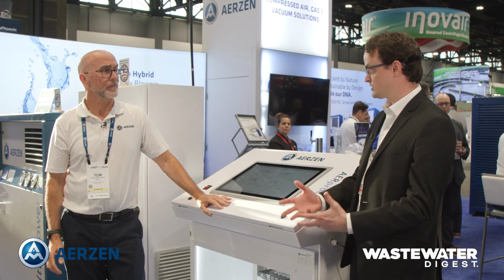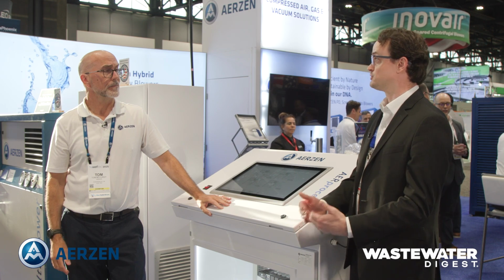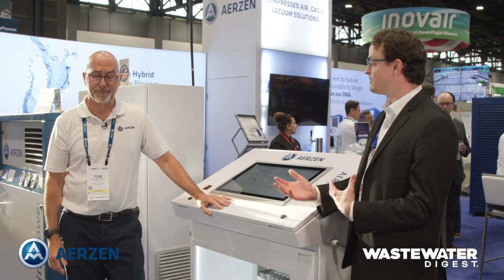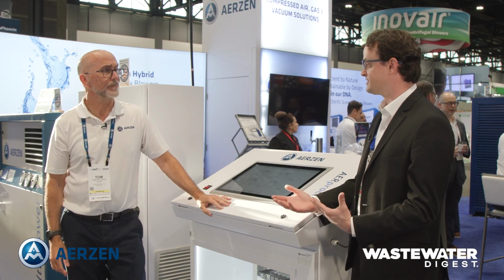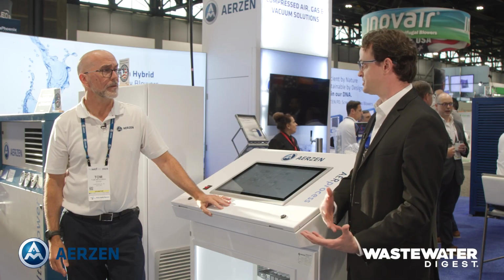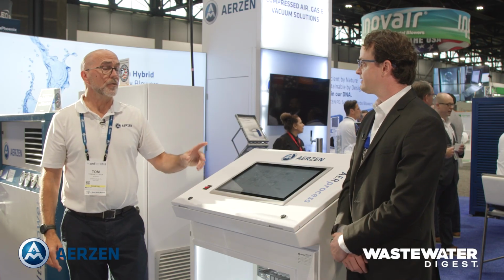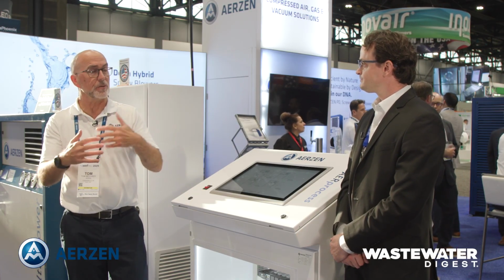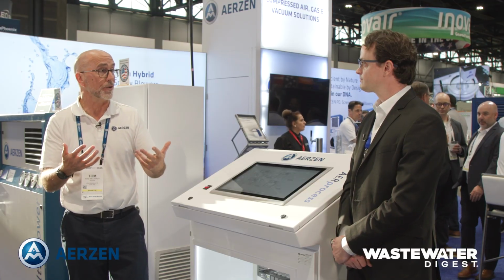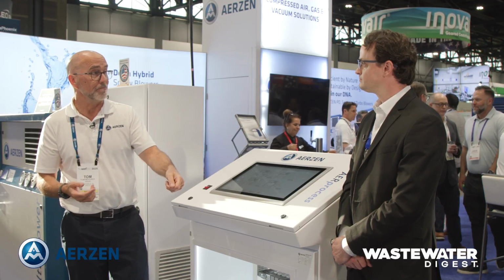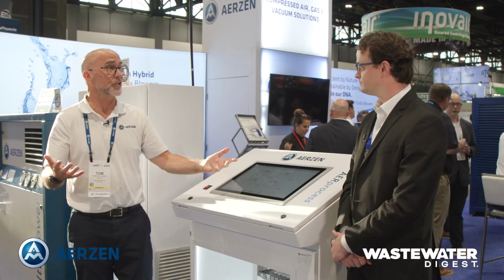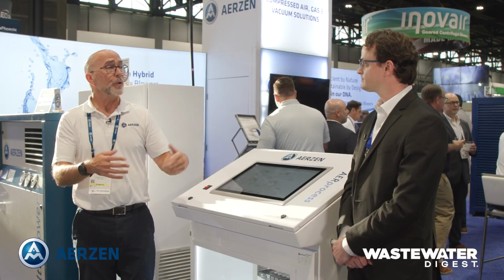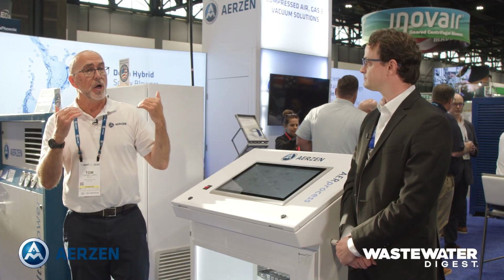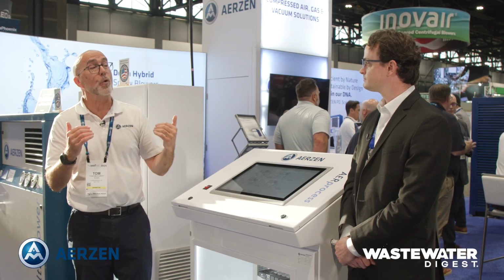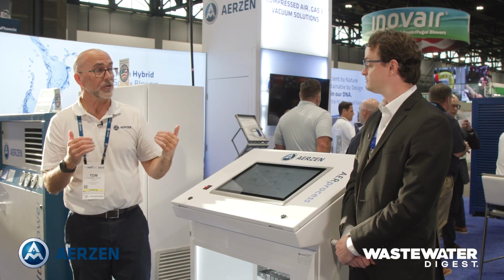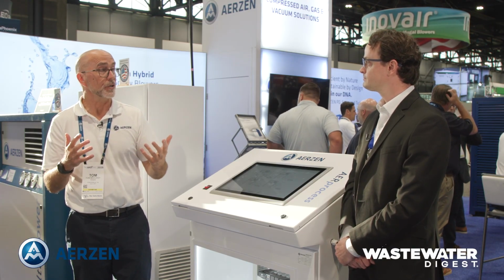One of those things that wastewater systems are always trying to do is reduce their energy as well. So when you think about improved DO and improved dissolved oxygen, what is the impact there on the energy side of that equation as well? Well, compared to a system with manual control, where they're basically just manually measuring the DO, and there are still systems out there, to put in an AERprocess can save, we've documented this, over 40% on the energy costs compared to what they're doing uncontrolled.